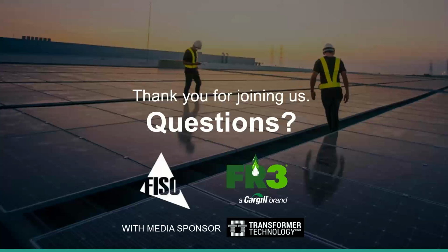We can share some numbers, especially here in the US, where we would estimate something around 12 to 14% of the new transformers already being filled with FR3. The number is much smaller in Europe, but we hope it will grow. Maybe I can ask you the question. In the early times of using natural esters, it was used for medium voltage transformers. But nowadays, the rated voltage of the transformers filled with FR3 has still increased. What is the highest rating and voltage at the moment for power transformers filled with FR3?